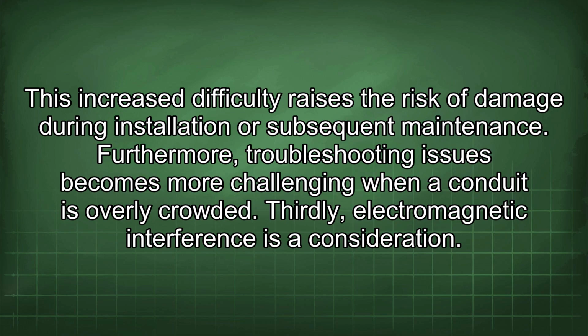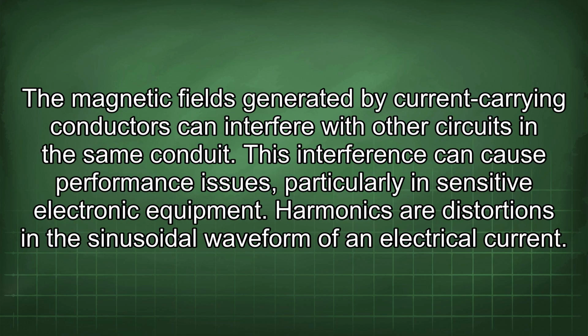Thirdly, electromagnetic interference is a consideration. The magnetic fields generated by current-carrying conductors can interfere with other circuits in the same conduit. This interference can cause performance issues, particularly in sensitive electronic equipment.